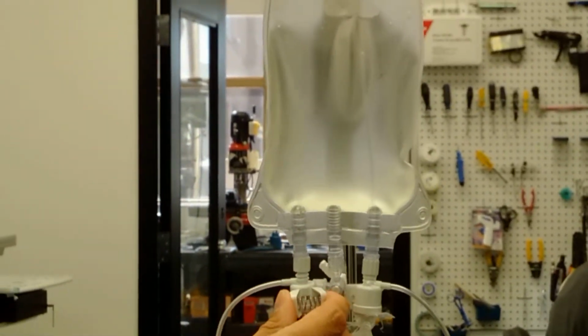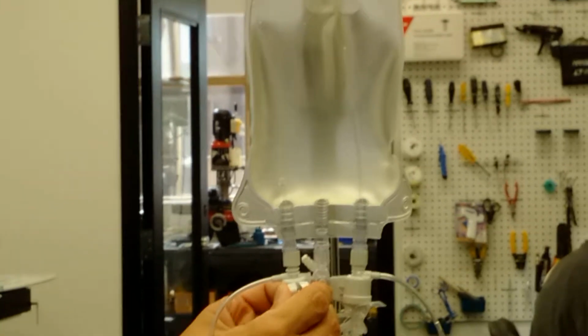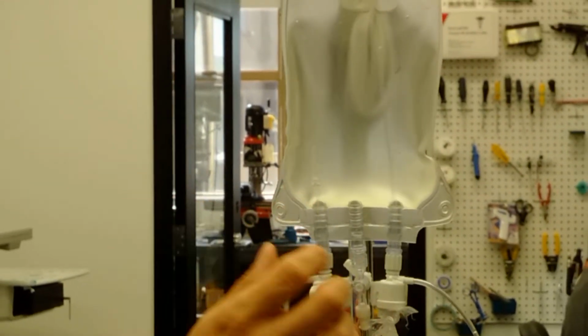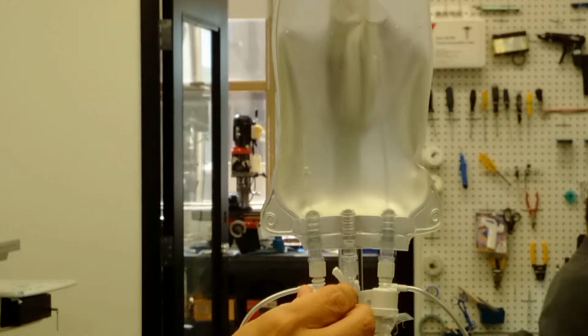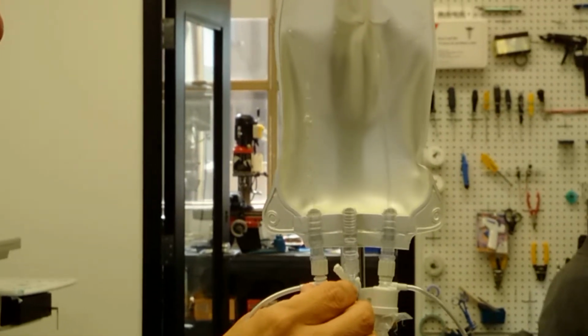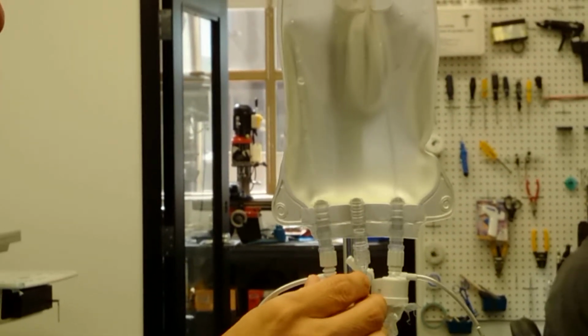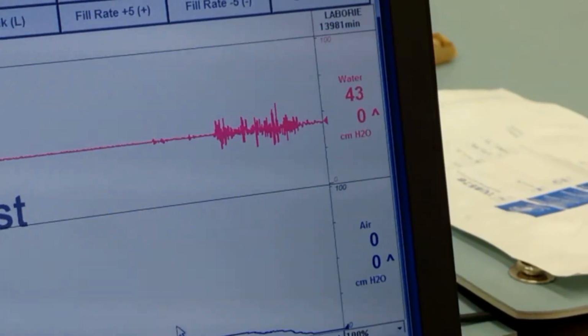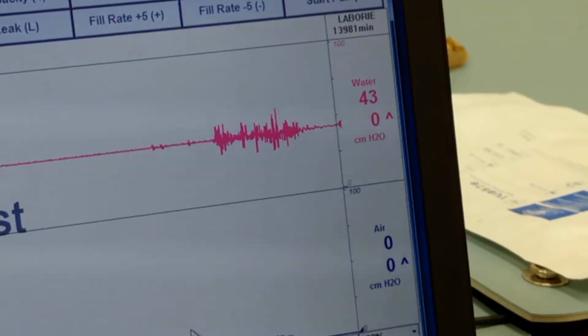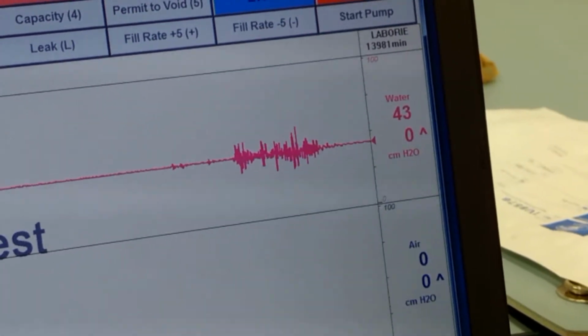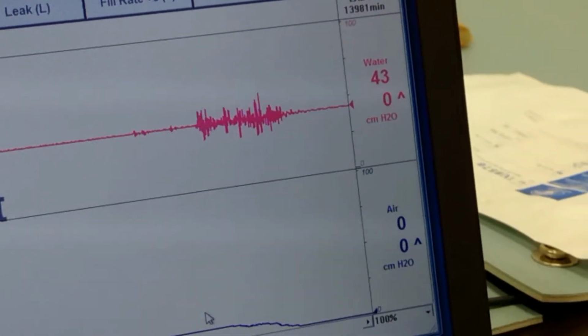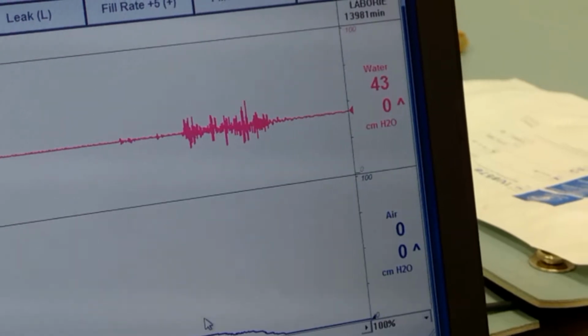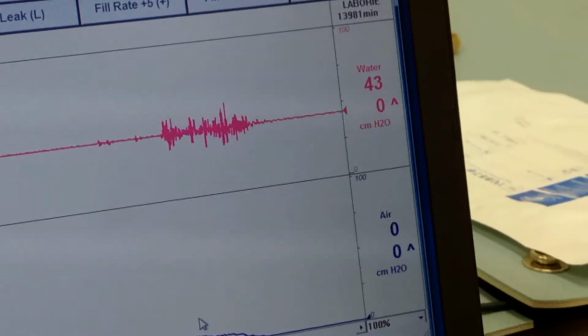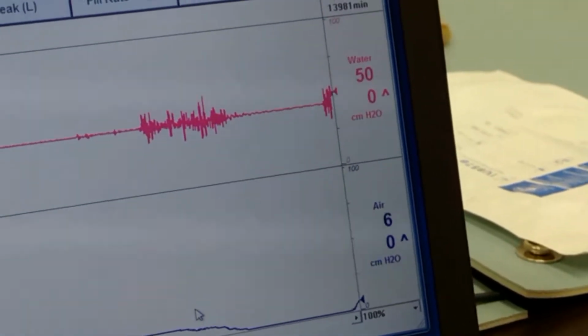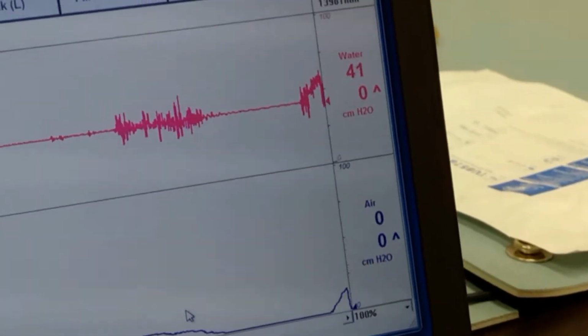I'm going to raise the position of the catheter inside the bladder. So here's the balloon right here at the bladder neck, and I'm pushing it up. I'm not changing the position of the bladder or the position of the transducer. When we go back and take a look at the readings, now the air charge is showing 0. As you can see, the amount of catheter we put in the patient is critically important for the kind of baseline pressures we're going to get. It's still responsive, so if I squeeze the bladder, I'm still going to get a response.